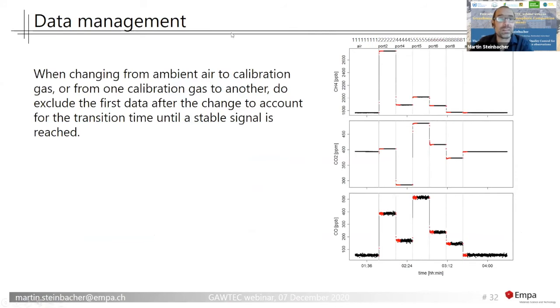This we can see, for example, here. We started to measure ambient air, and then we switched from air to port 2, port 4, port 5, 6, 8, and back to air. It means we measured 5 different high pressure cylinder reference gases. And then you see the red data are the ones that are rejected, because it usually takes some time after switching the valve until the signal is stabilizing, and then only the second part is used for determining the reading of the instrument when a gas that was connected to port 6, let's say, was measured.